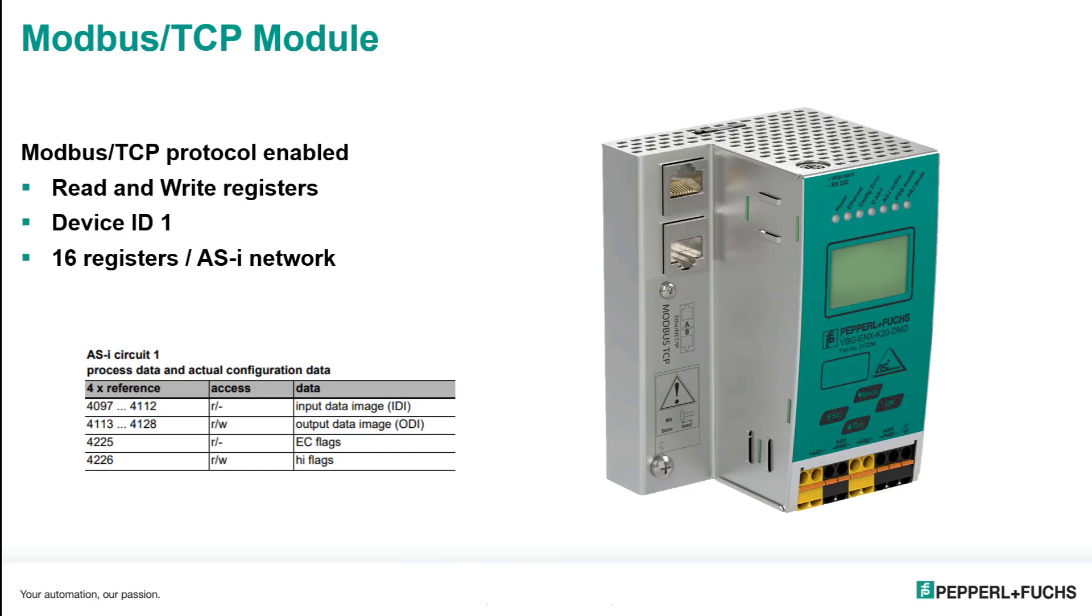So let's dig into what the Modbus device can do. I'm going to read and write 16 registers, and these are 40,000 registers. I will read the input starting at 4097. This just comes directly from the specification of the device, so don't be afraid of that.